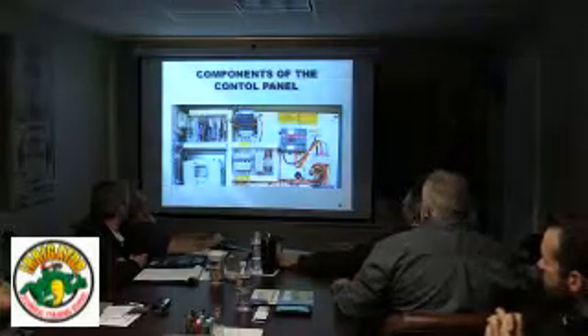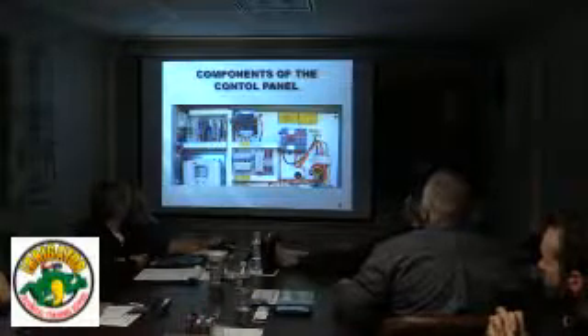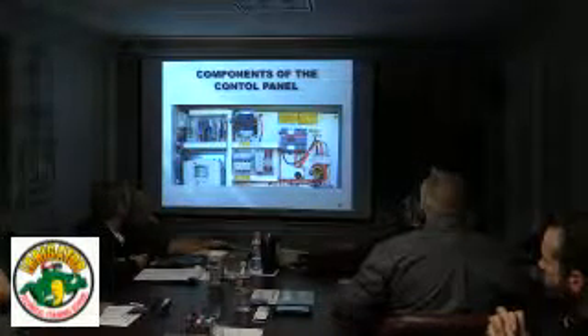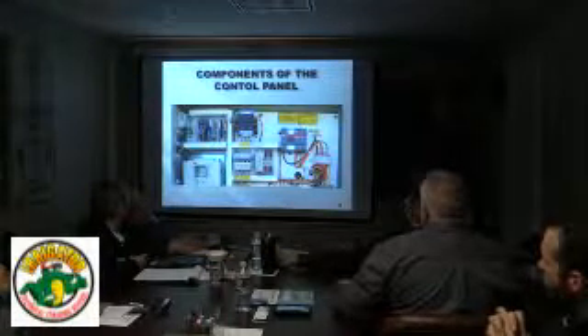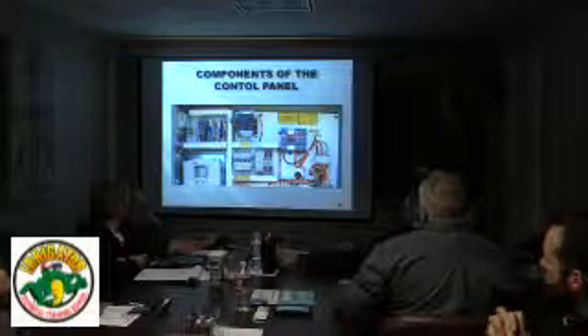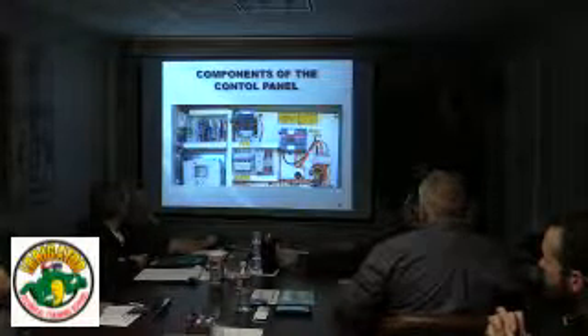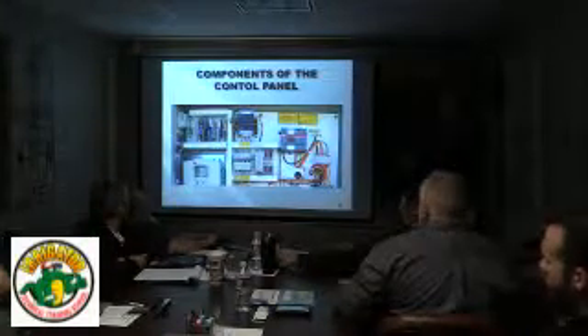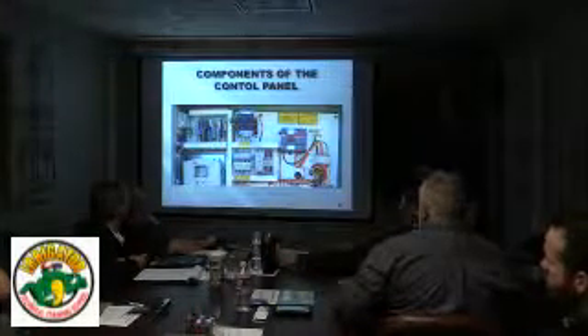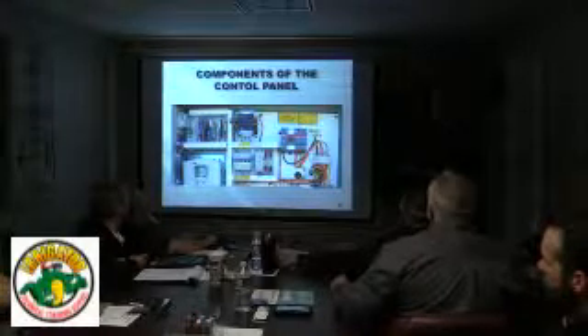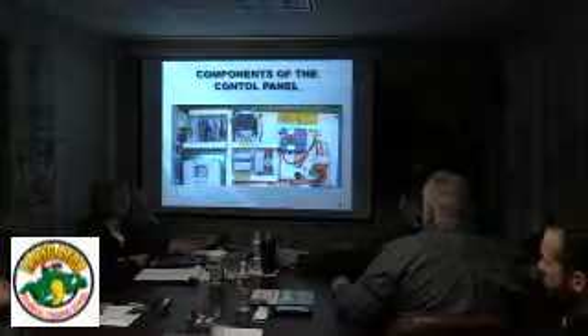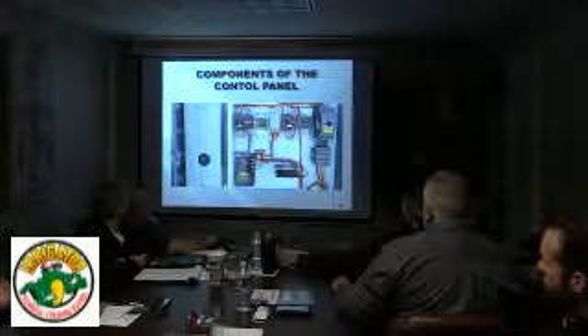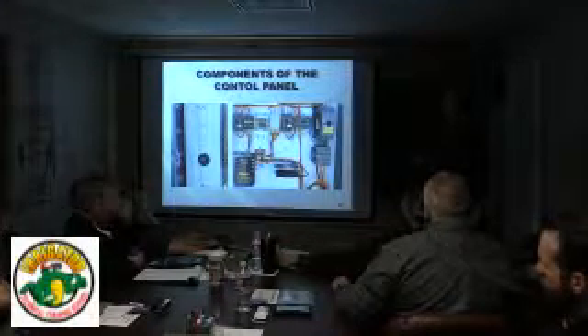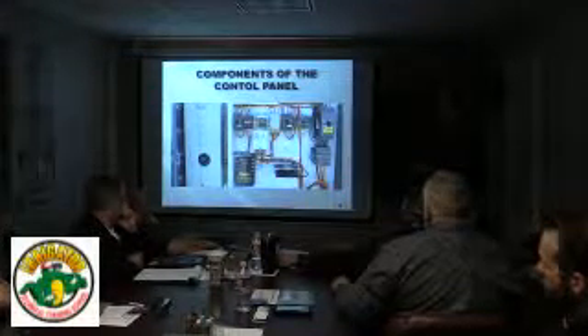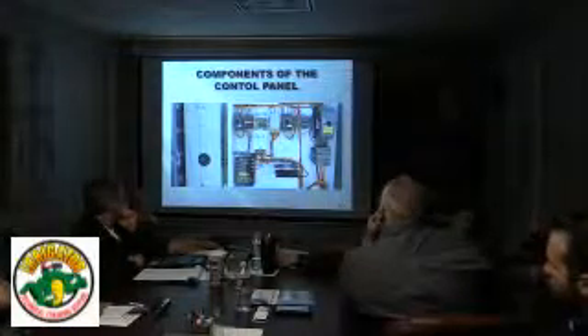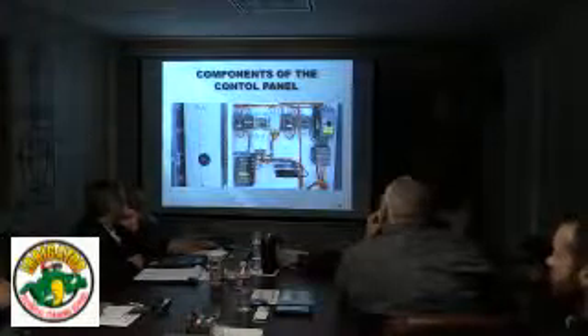Typically, after our power comes through our main disconnect, we'll have some kind of a distribution block, and that's where we distribute the 480 volts to all the different components. So like on this one, we have main power coming into a main contactor. We're coming over to the top of different items here, up to the control transformer. So we distribute our 480 volt from there on down. Here's the next view. You can see power comes in through this overload and through a contactor and over to the drive. It comes down to the top of the contactor, these other breaker overloads here.